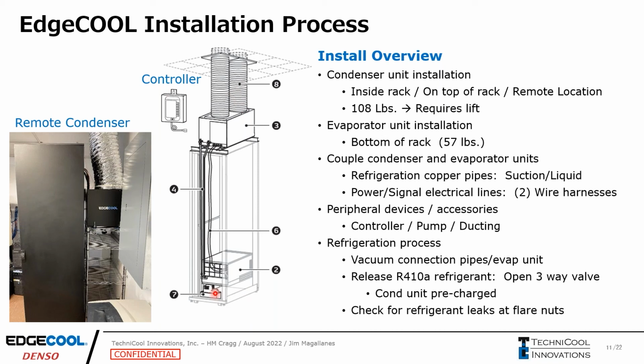Once those are all set up, you go into your refrigeration process. You put a vacuum pump onto these valves here. You vacuum out the pipes that you connected and the evaporator system. Once that's done, the condenser unit is pre-charged with refrigerant. So you just open up these valves, release the refrigerant into the whole system, check for leaks, and you're ready to go. You're ready for cooling.